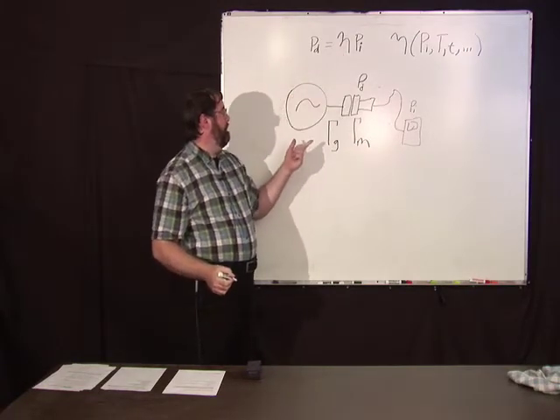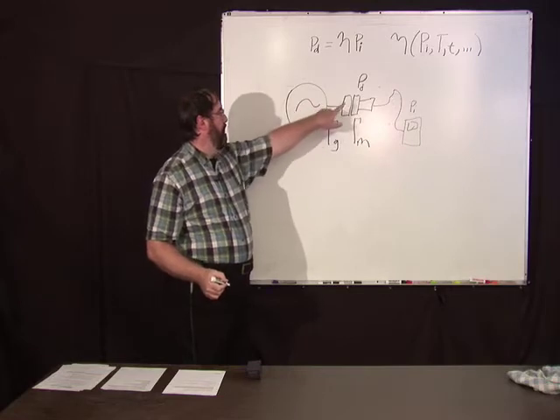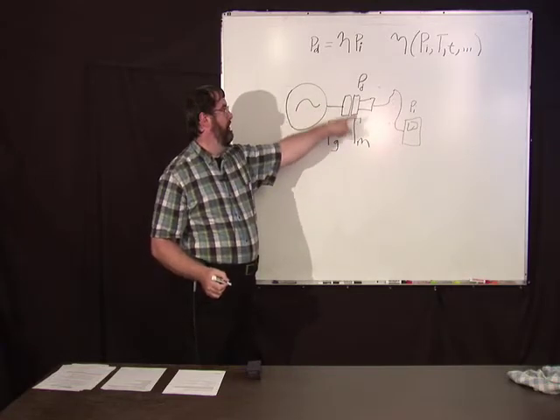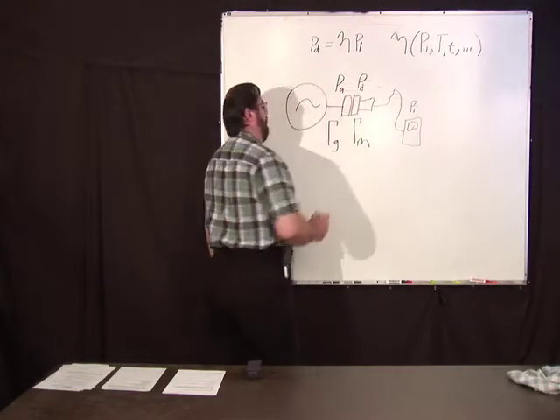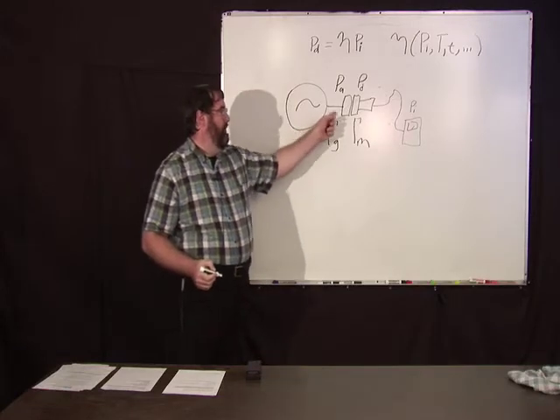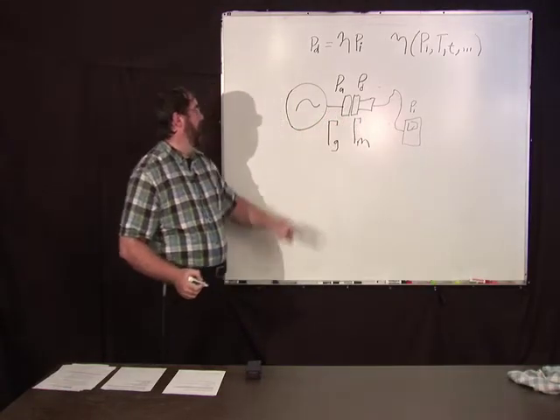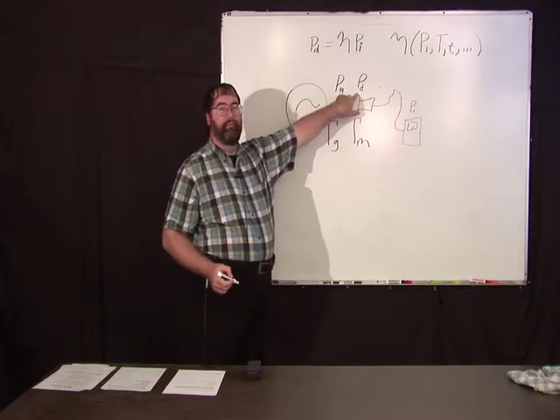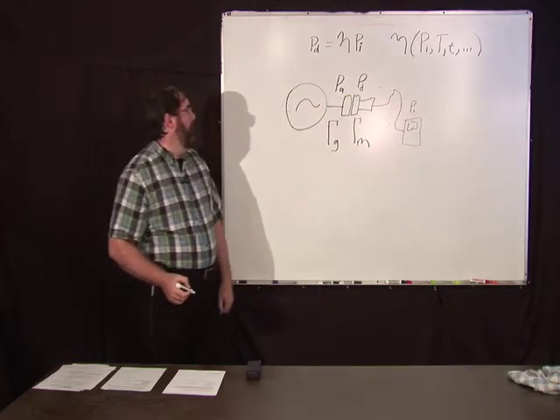Now this eta here might be a function of the indicated power - for instance, this could be some sort of detector that has some sort of square law response. So this correction is going to depend on the square of the indication. It might also be a function of temperature, might be a function of time, it could be a function of all kinds of things. But in a lot of cases, you want to find out what this is.